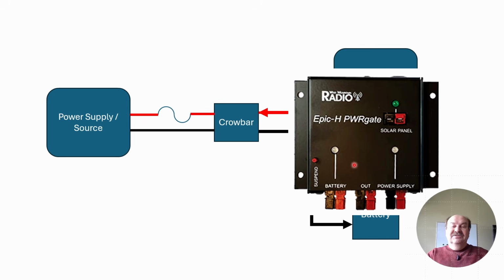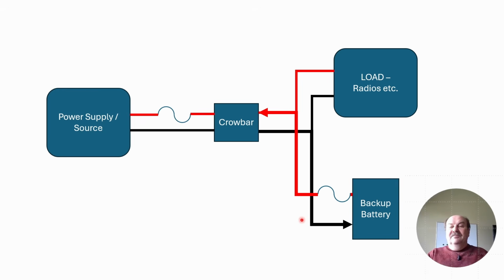So this is another option. And honestly, anytime you have a battery connected into your system, or any power source at all, you should really have a fuse or circuit breaker on every item that's providing power. The power supply, the battery, a solar panel - everything should have some circuit protection, so that if a short circuit happens, the wiring is protected, and if an overcurrent happens, your equipment is protected. That's the key issue with this arrangement that I wanted to make sure you were all aware of.